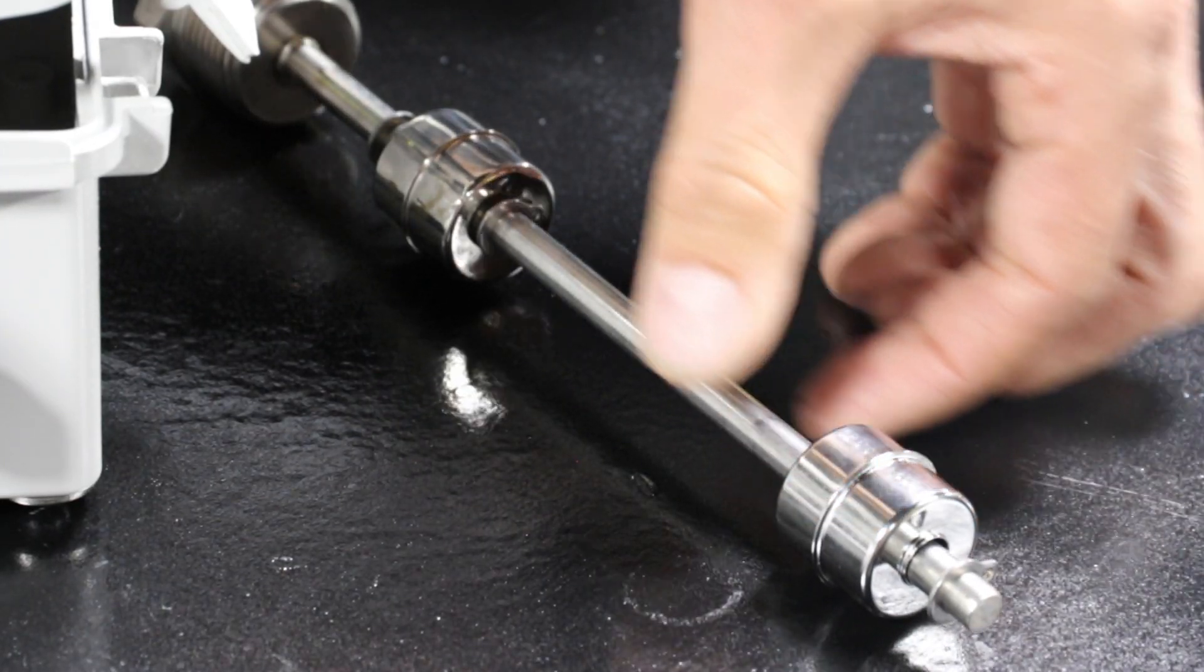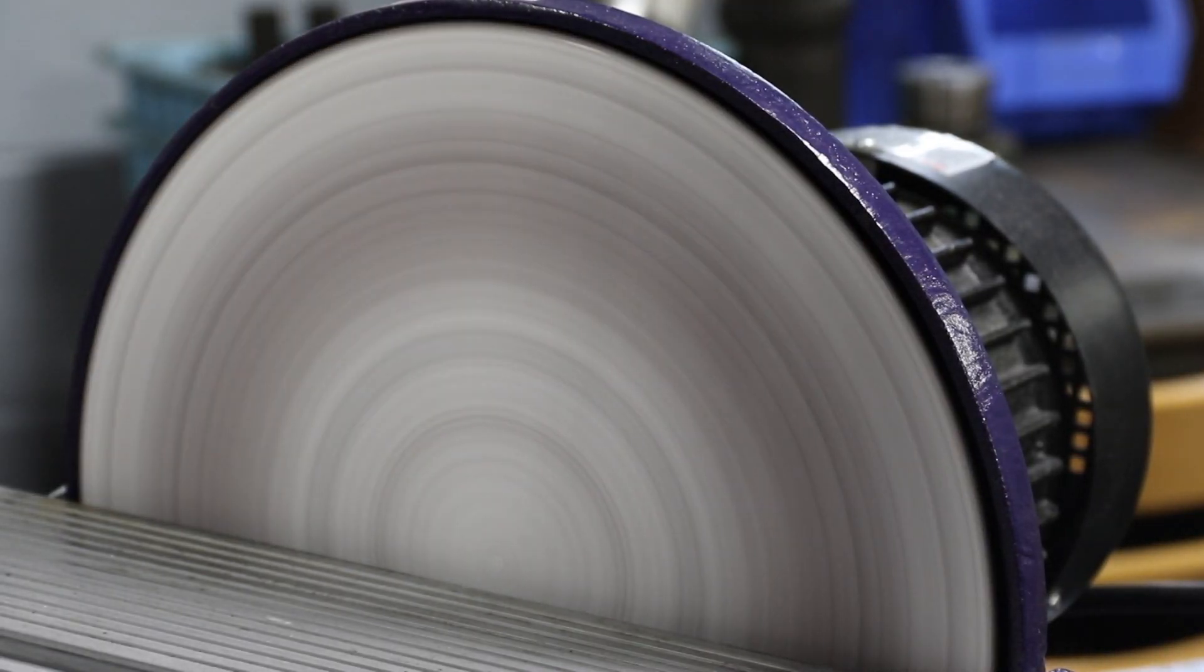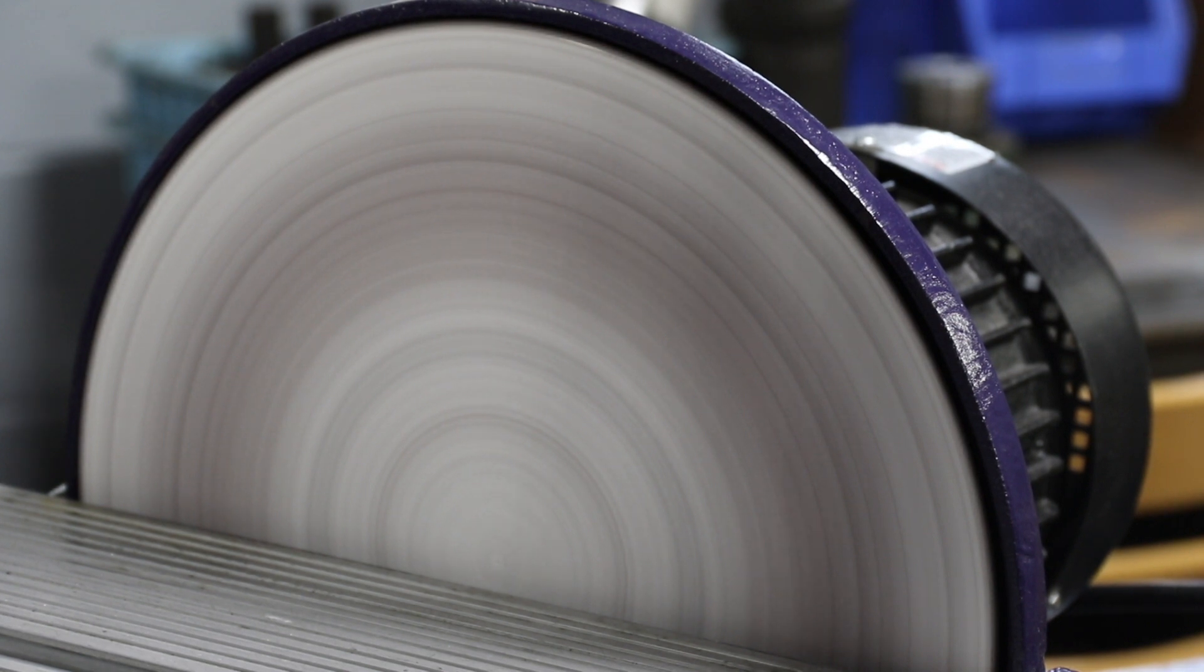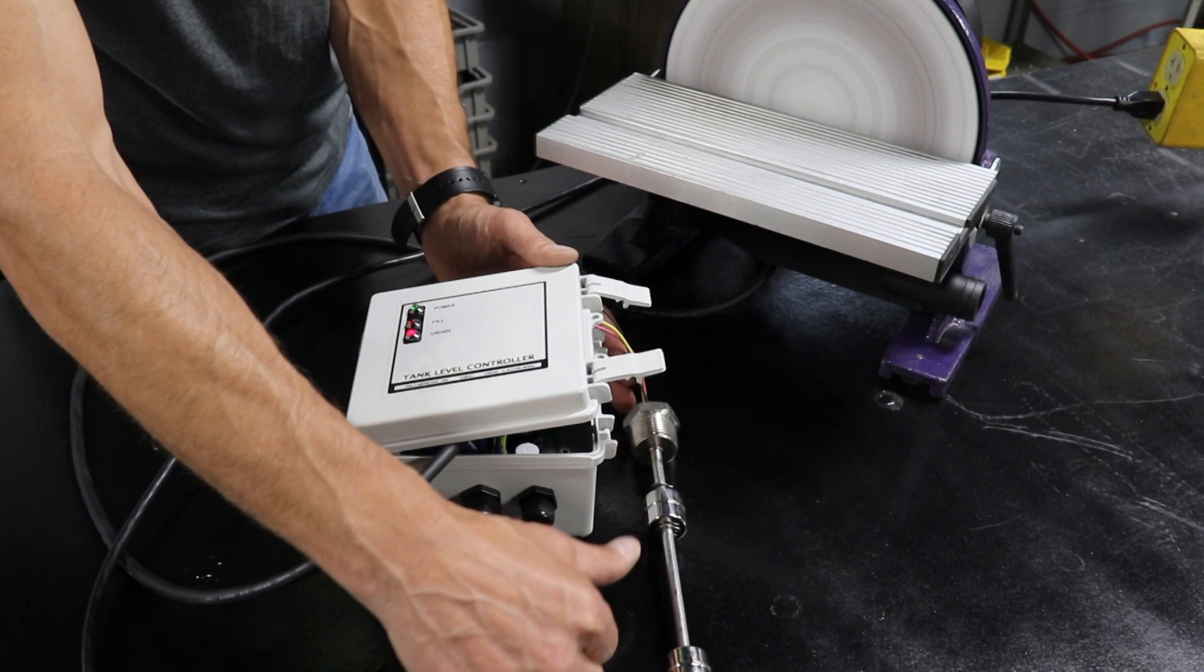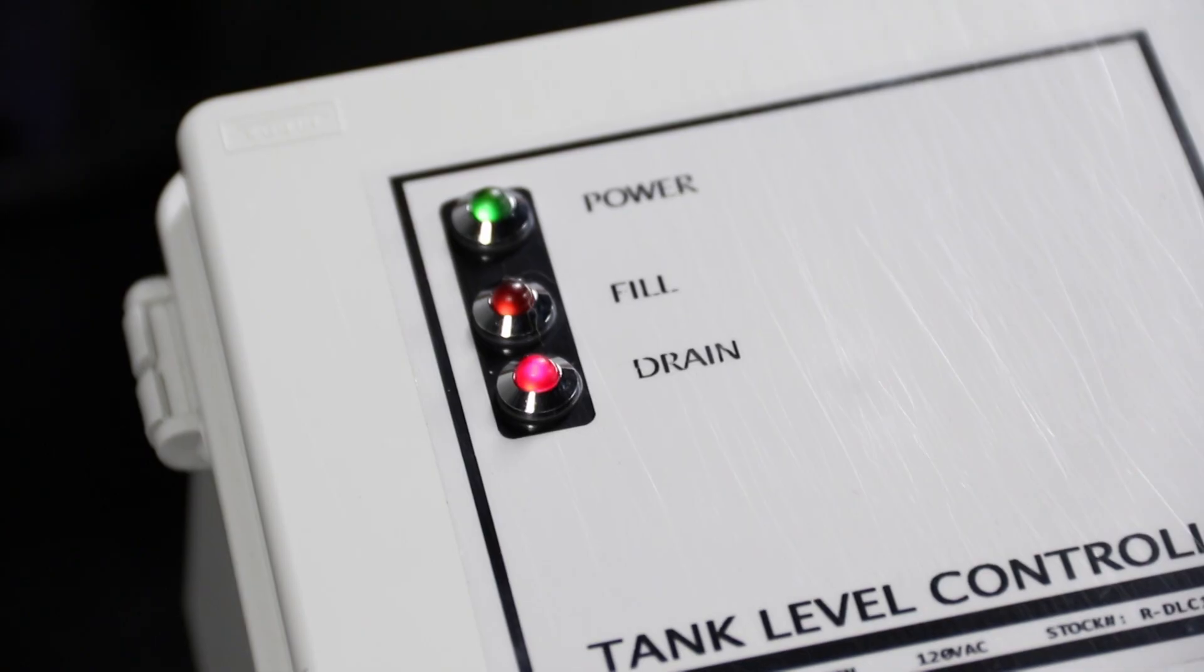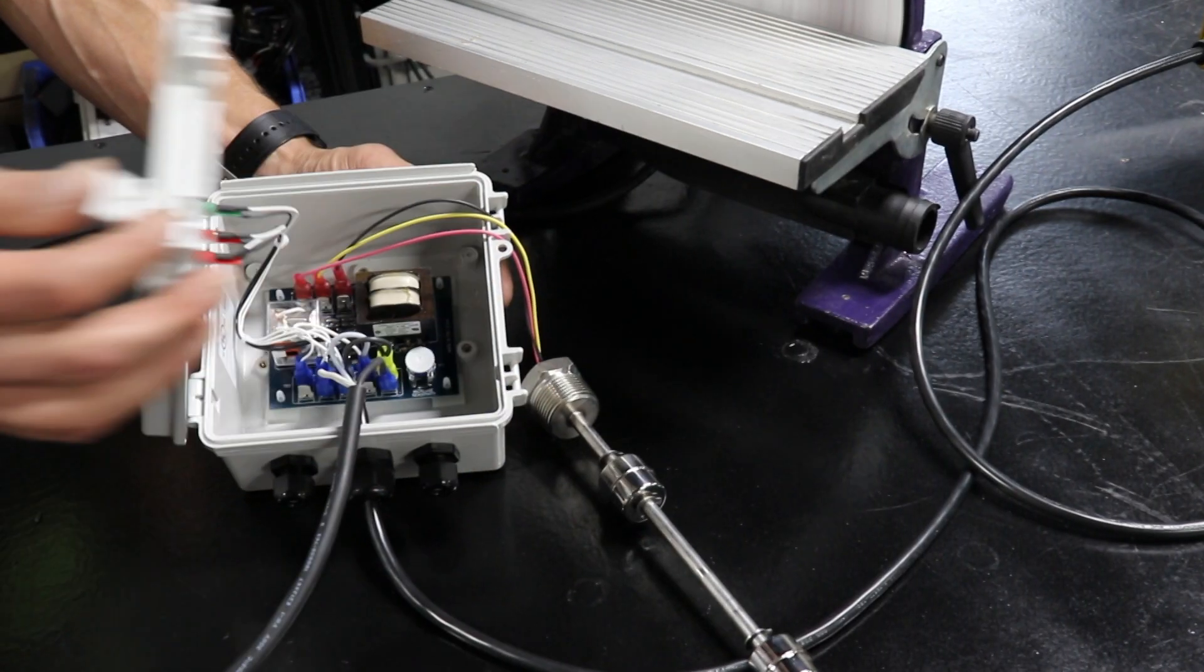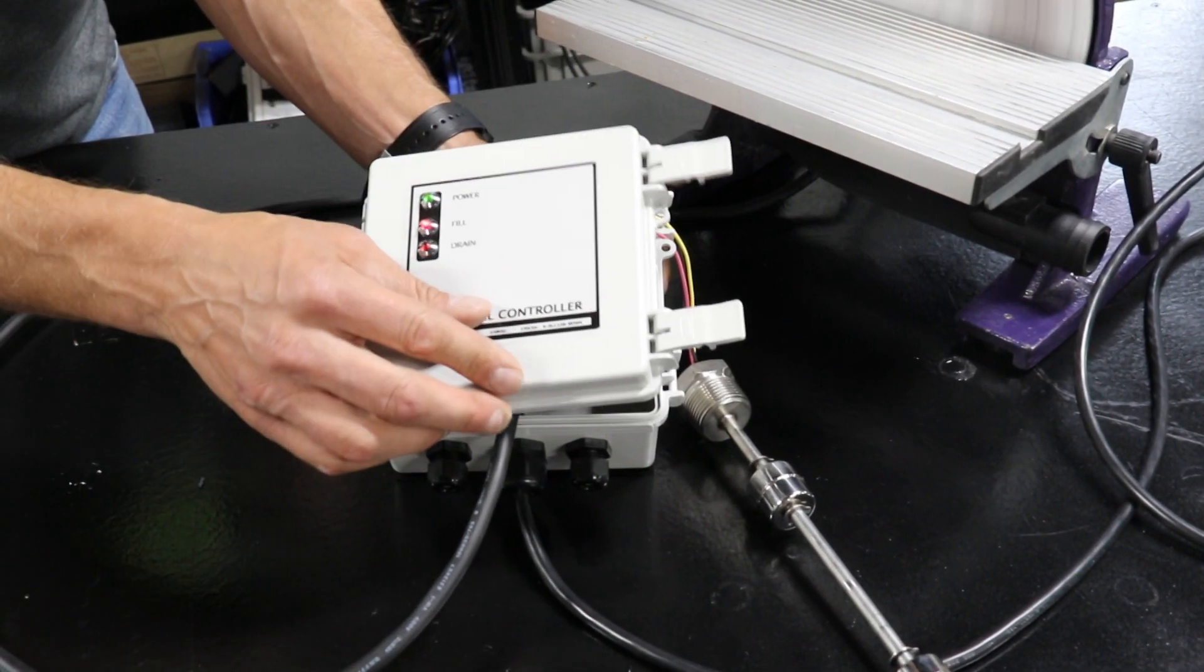When the low float rises nothing happens but when the high float rises the pump turns on and our tank would begin to drain. As the tank drains the high float drops and then the low float drops signaling the pump to turn off. And that's how you hook up a level switch to a tank level control relay.